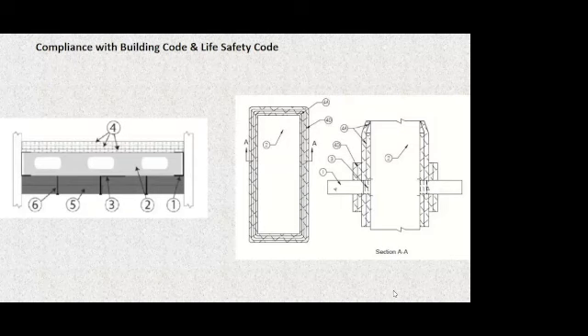And that's worse than doing nothing at all, because that has people coming into the building, whether it's the occupants, whether it's the structural fire response. These people think when they look up that they have what they're supposed to have in the way of protection. The best analogy I can make is like those newspaper articles we see when occasionally you'll find some inspector who popped his head above a ceiling doing an inspection and he found no piping behind the sprinkler head.